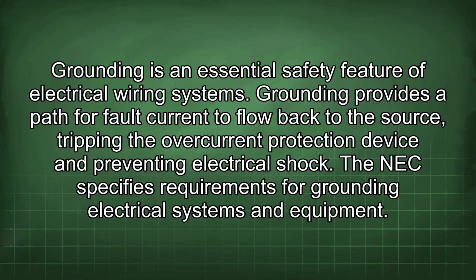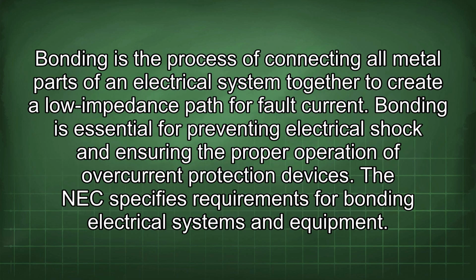Grounding is an essential safety feature of electrical wiring systems. Grounding provides a path for fault current to flow back to the source, tripping the overcurrent protection device and preventing electrical shock. The NEC specifies requirements for grounding electrical systems and equipment. Bonding is the process of connecting all metal parts of an electrical system together to create a low impedance path for fault current. Bonding is essential for preventing electrical shock and ensuring the proper operation of overcurrent protection devices. The NEC specifies requirements for bonding electrical systems and equipment.